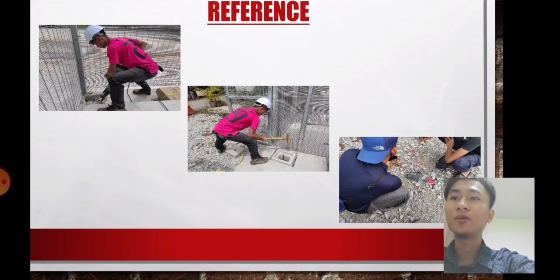Okay, the procedure of making this earthing installation is to make sure all tools and equipment are in good condition, and read the label first before starting to use them. After that, identify the place, length, and width for the chamber by using measuring tape. Before beginning the digging work, cut the line with the grinder and then start digging the hole by using hammer drill to the required depth of the chamber.